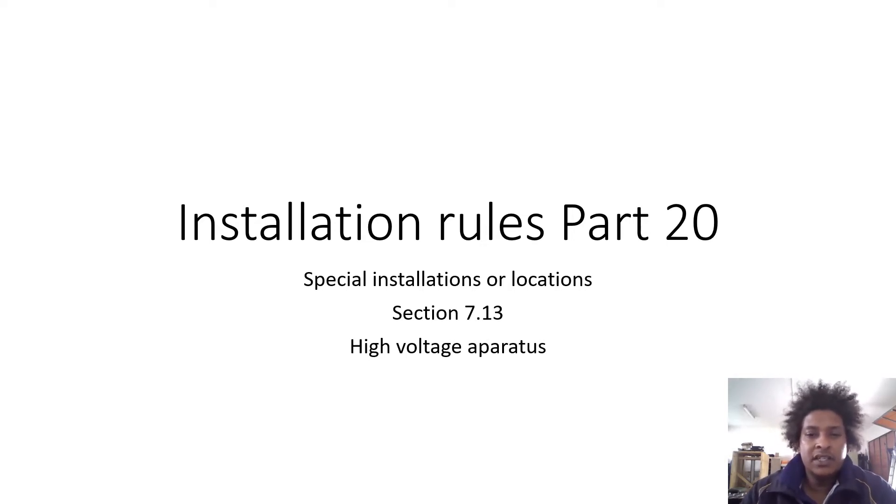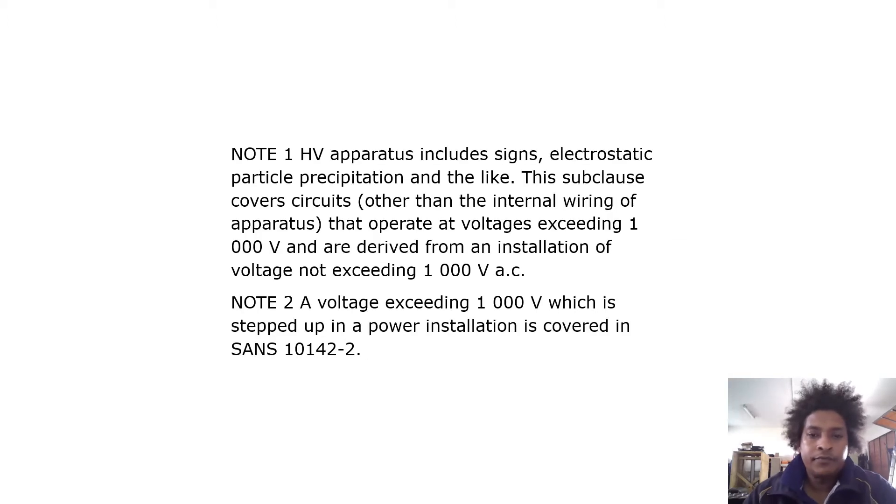These special installations specifically cover high voltage apparatus. Per section note one, HV apparatus includes signs, electrostatic particle precipitation, and the like. The subclause covers circuits, other than internal wiring or apparatus, operate at voltages exceeding 1000 volts derived from an installation not exceeding 1000 volts AC. Note 2: a voltage exceeding 1000 volts stepped up in a power installation is covered in SANS 10142-2.